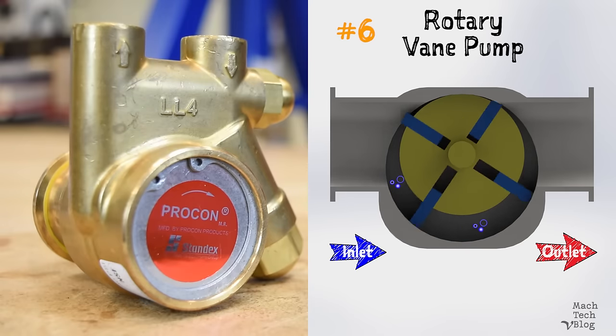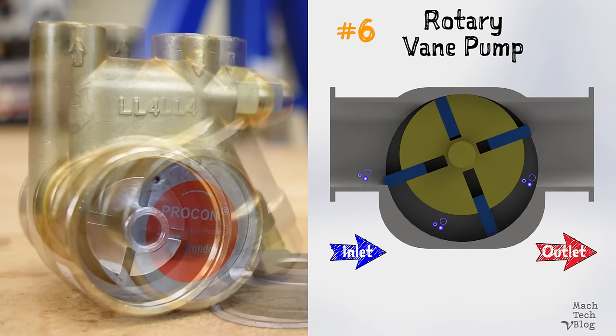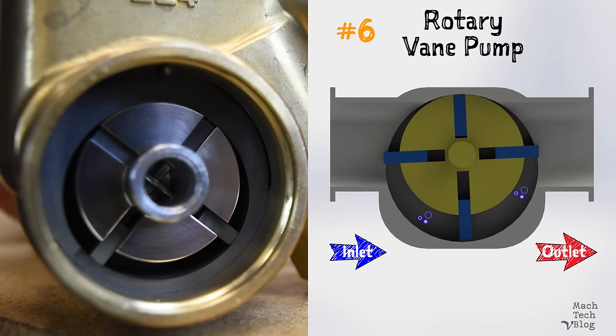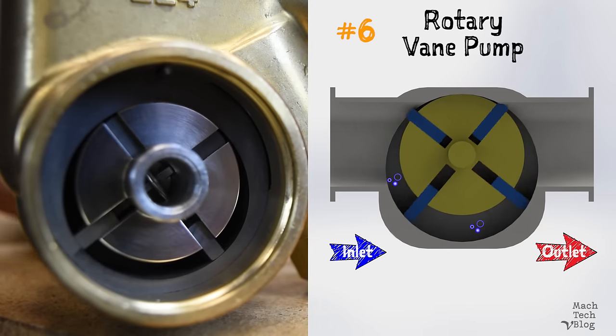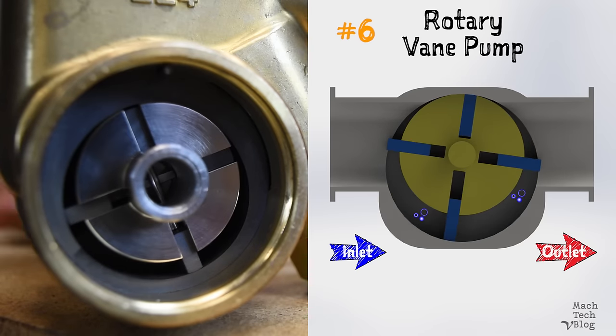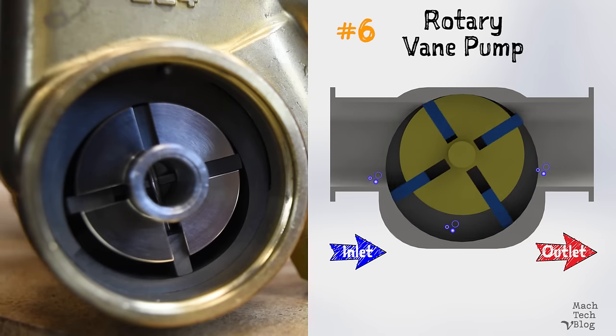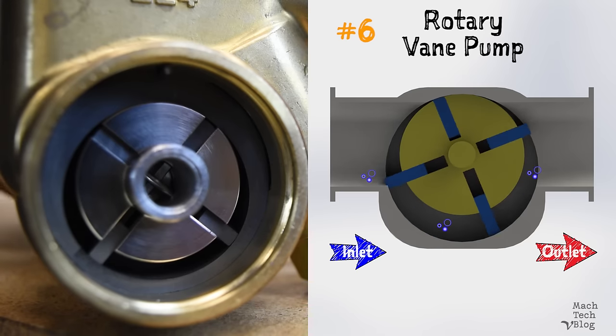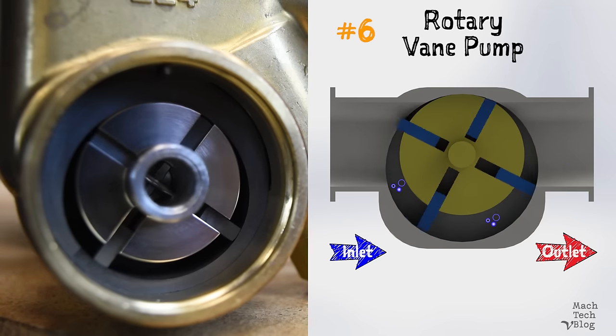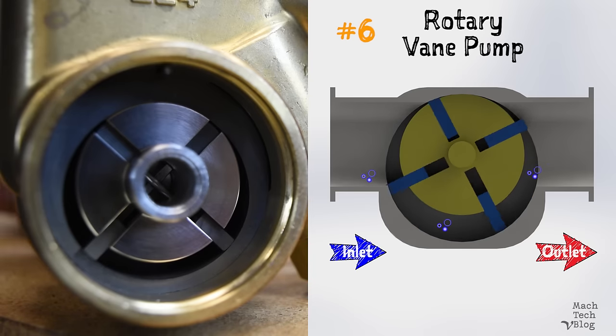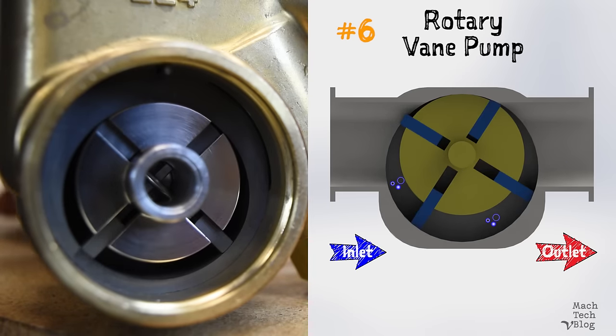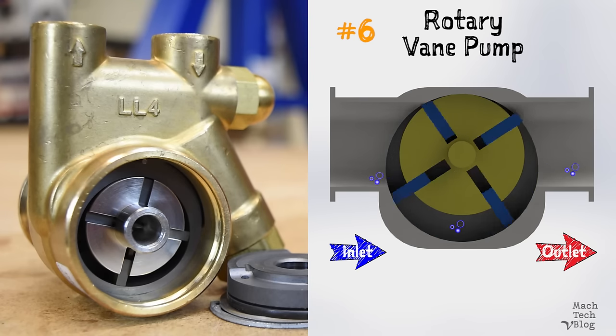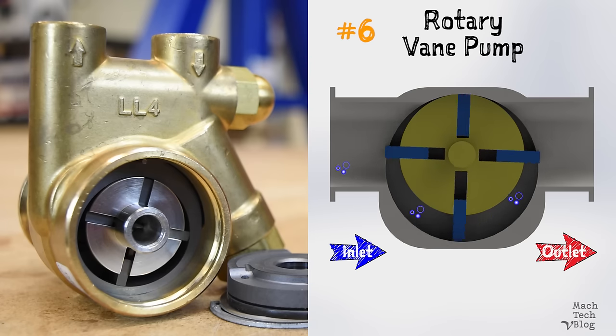Pump number six is the vane pump. A vane pump rotor has slots in it for sliding vanes. Centrifugal force flings the vanes out to contact the inside wall of the circular housing, forming a sealed chamber. Since the rotor is offset in the housing, the vanes extend and retract during rotation. The chamber increases in size at the suction inlet, drawing fluid in. At the discharge outlet, the chamber decreases in size, pushing fluid out. The nice thing about vane pumps is that they automatically compensate for wear, because the vanes are constantly forced against the wall of the housing.